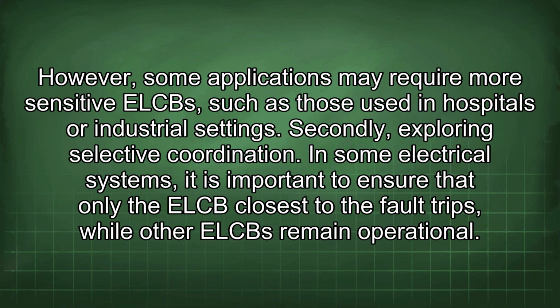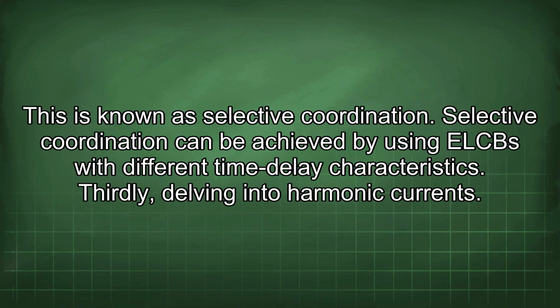Secondly, exploring selective coordination. In some electrical systems, it is important to ensure that only the ELCB closest to the fault trips, while other ELCBs remain operational. This is known as selective coordination. Selective coordination can be achieved by using ELCBs with different time delay characteristics.